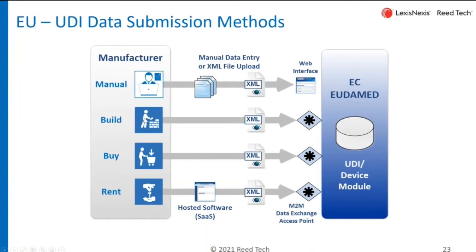Your other option is to use a system that automatically manages that information and transmits data in an automated, machine-to-machine fashion to the EUDAMED database. You have a couple of options there: you can build a system, buy and install a system, or what we refer to as 'rent' a system — subscribing to a Software-as-a-Service type of system. That's actually what Reed Tech offers: you connect to our platform and we handle all the mechanics — the protocol, building the XML file, and so on.